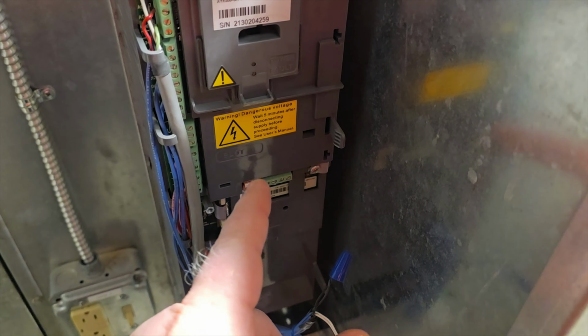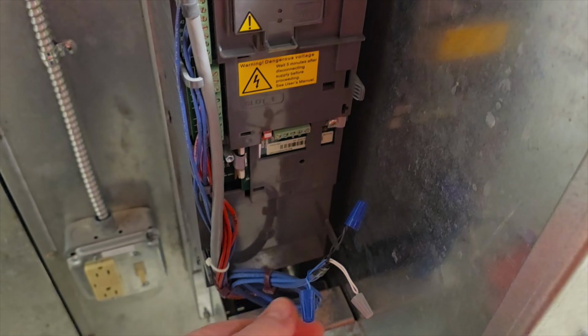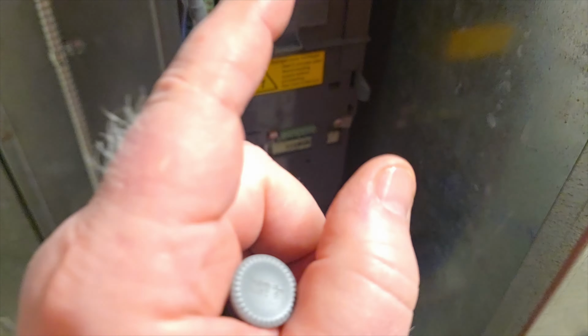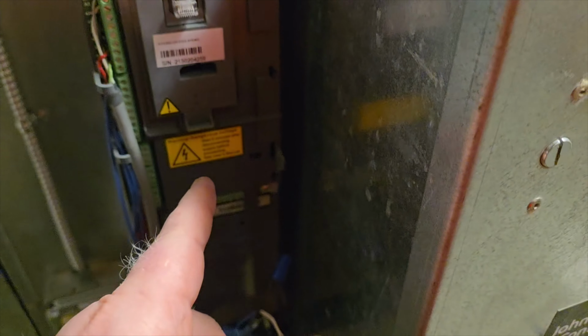Let me walk over and show you. I've disconnected this VFD from the trunk. I've just got it capped off for right now. Something about this VFD is contributing to the network issue. I literally shut power off and it started dropping immediately, so I've got it disconnected here. But there's definitely an issue in this drive that is causing an issue with the trunk. Bus Health Index is a good little troubleshooting tool to make your job a little bit easier.